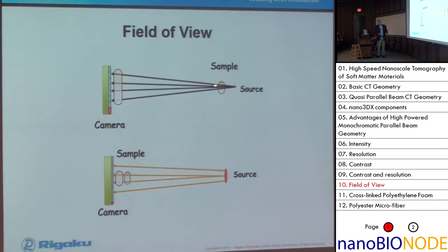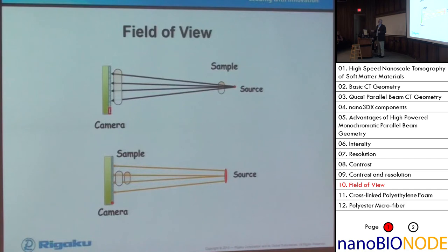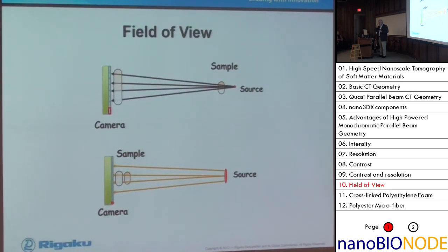As we move the sample further away from the source - which we can do if we don't need the magnification factor - we get a larger field of view. That is one of the limitations of CT: to look at something at 500 nanometers, you're looking at a field of view of maybe 0.7 by 0.7 millimeters, so it's small. We do talk about tomography as being non-destructive - unless you need to destroy the sample to get it in the machine. Given that the sample fits in the machine, there's nothing you need to do to it. In most cases, you do need to get the sample down to a size such that it is completely encompassed within the field of view.